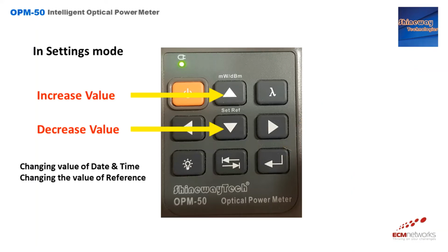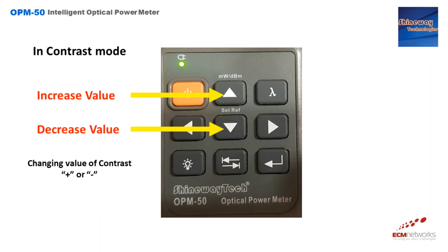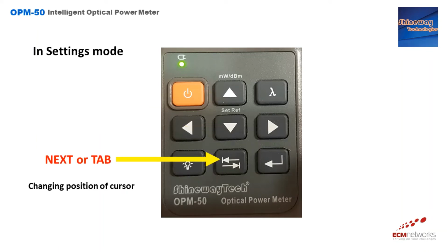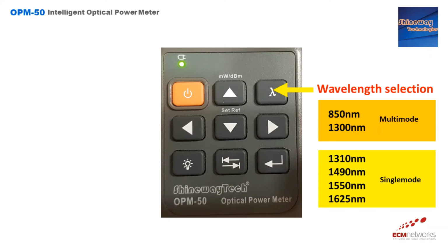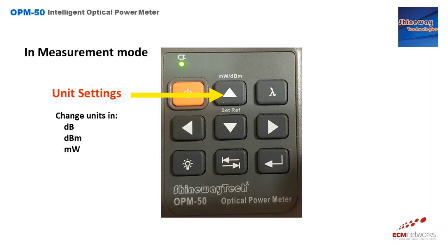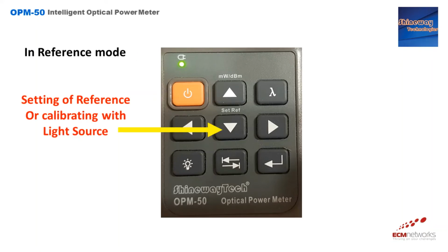In settings mode like date and time setting and changing the reference value, the up and down keys are used to increase or decrease the value. In contrast mode, the up and down arrows are also used to set the contrast of the equipment display. The next or tab key is pressed to change the position of the cursor. The wavelength key is pressed to change the wavelength setting of the OPM50 to be measured. In measurement mode, the up arrow is pressed to change the power units from dB to milliwatts. In reference mode, the down arrow is pressed to zero out or reference the OPM50 to a stabilized light source.